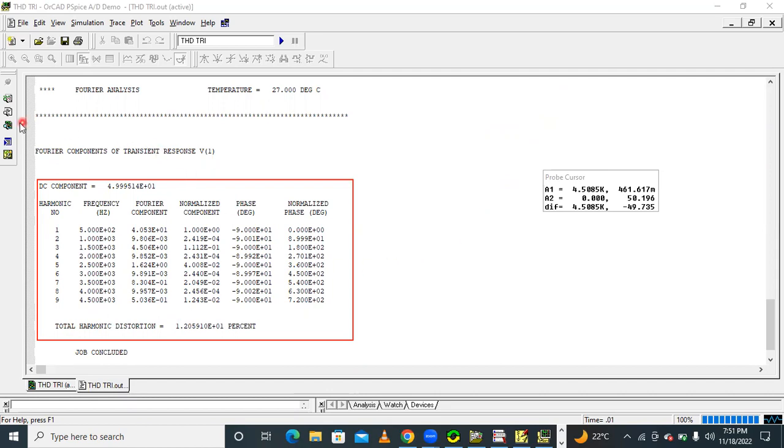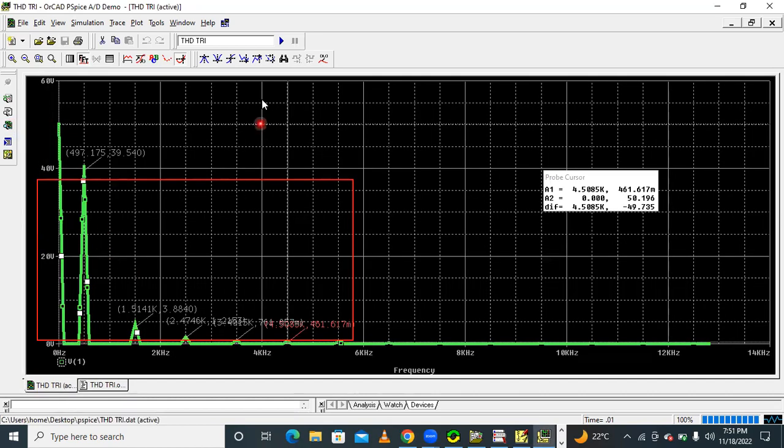So here in this waveform, 500 Hz is the fundamental. The corresponding fundamental voltage is 39.540, and the next harmonic voltage at 1.51 kHz is 3.84, and here corresponding to 2.5 kHz it is 1.32. So like this, different harmonics generate voltages. Then how to find the THD for these different harmonics? By using the THD formula: square of the harmonic voltages divided by the fundamental, under root.